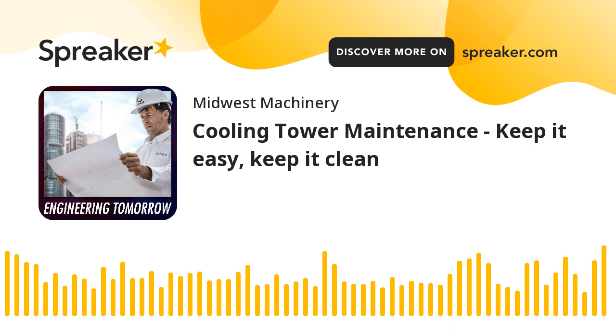Right, especially the environment that they're in. They're going to see all the seasons of the year. Whether or not the cooling tower is being used during all the seasons might become a factor as well. That really just, you need to be checking it, and you would be able to tell if it needed to be replaced or not. Yeah, that extreme weather really takes a toll on rubber for sure. All equipment, really. Yeah. Another thing that you're going to want to maintain or check initially is your fan pitch.